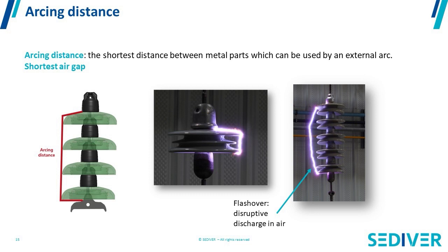Clearance is the distance between the conductor and the tower, which means you expect that if there is an arc, it goes from the conductor to the tower through air. On an insulator string, you have a parameter called arcing distance. This is the shortest distance an arc will follow going from the energized side to the ground side, without following the shape of the insulator. As you can see in the pictures, the arc goes from one side to the other of the insulator without following the profile. Several electrical characteristics of an insulator string are defined by the arcing distance — it is the shortest air gap the arc can take.